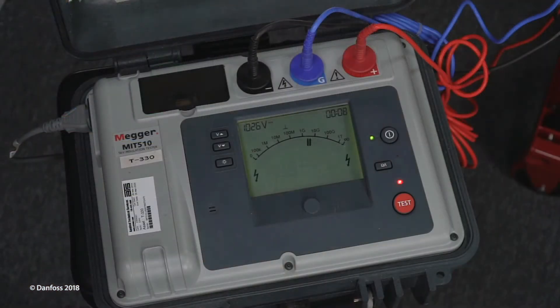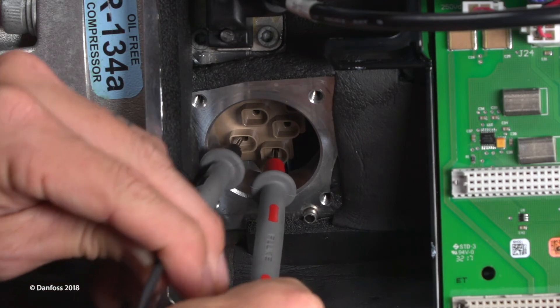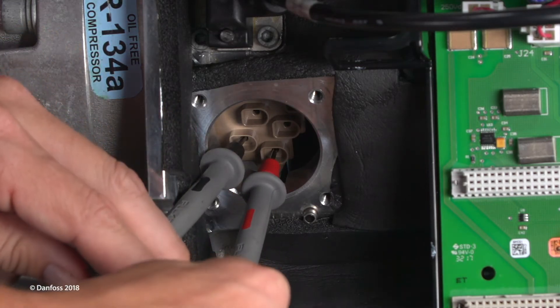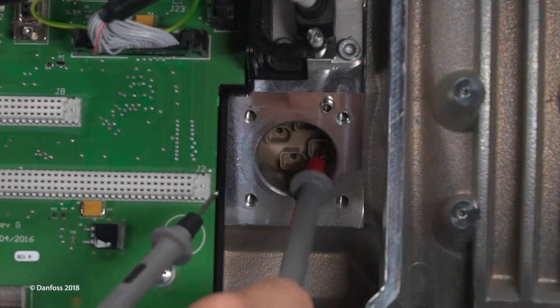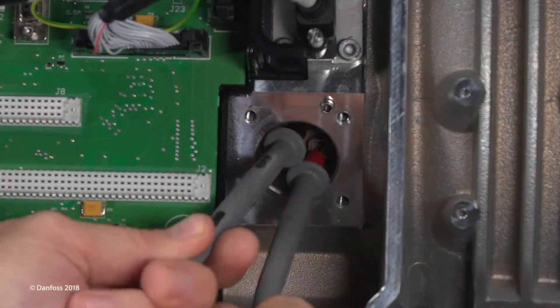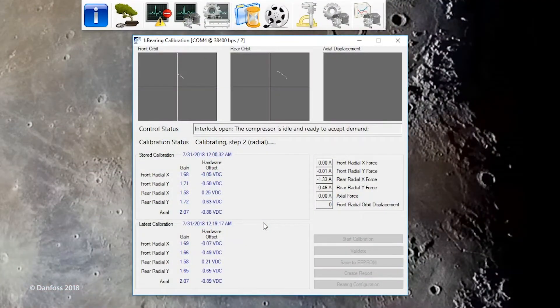Using a megohm meter (Megger), test the insulation of each coil to ground and between coils at 1 kilovolt. Insulation should be greater than 100 mega-ohms. If the values are not as expected, the bearing should be verified internally to determine if the issue is with the feed-through or bearing coil. Follow standard refrigerant recovery procedures prior to removing the feed-throughs. If the issue with the bearing system is not identified, the magnetic bearings may not be the source of the problem.